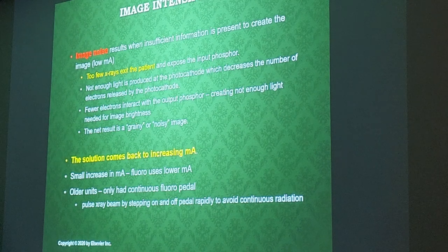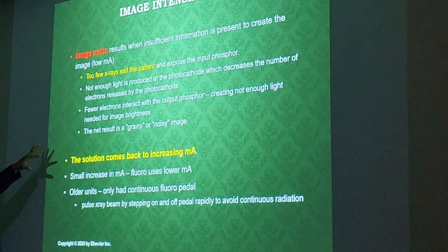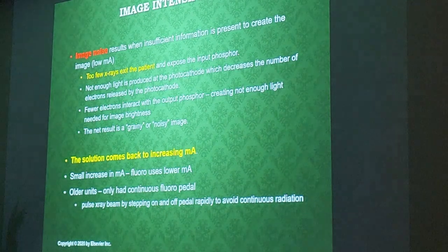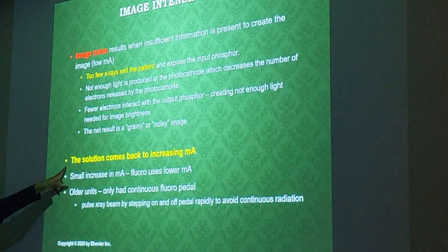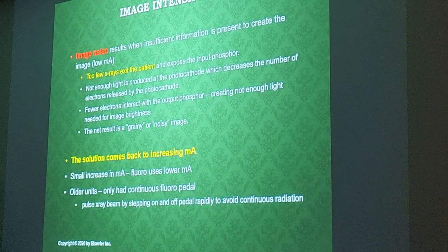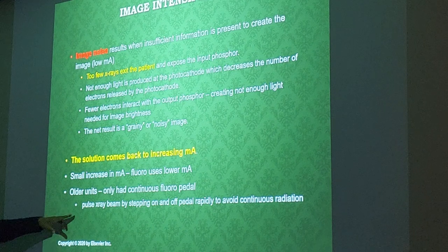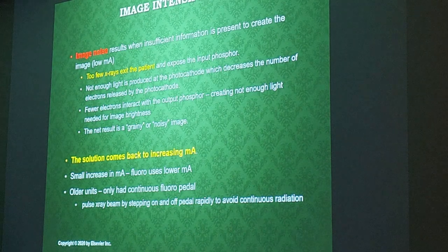Image noise can happen any time we have too low an mA — meaning too few x-rays exiting the patient, so fewer electrons interact with our output phosphor, creating less brightness and a grainy or noisy image. The solution is to increase the mA, but it's a small increase since fluoro uses a lower mA range. Using a pulsed x-ray beam is encouraged to keep patient dose low.